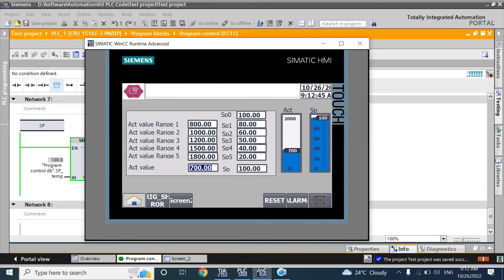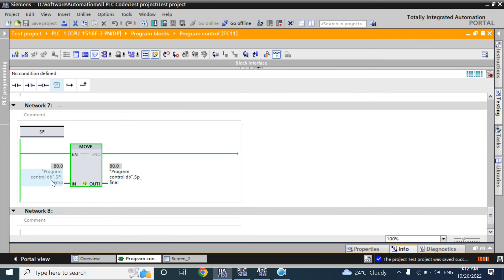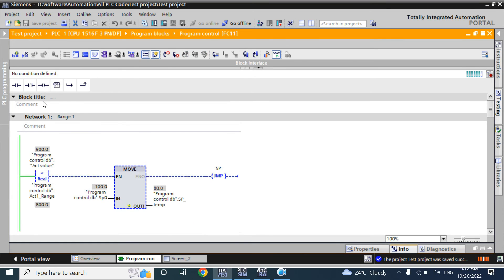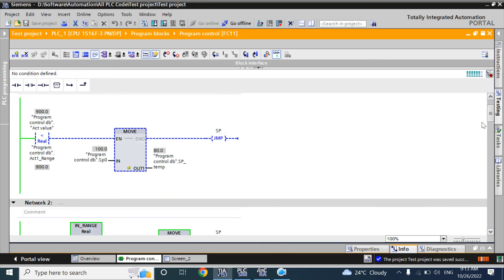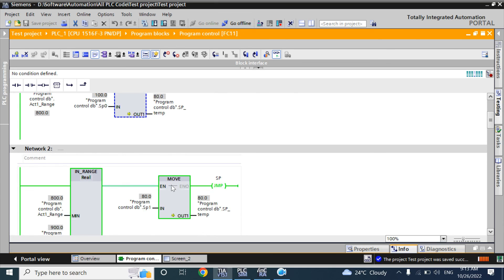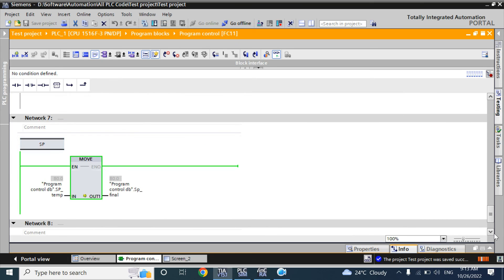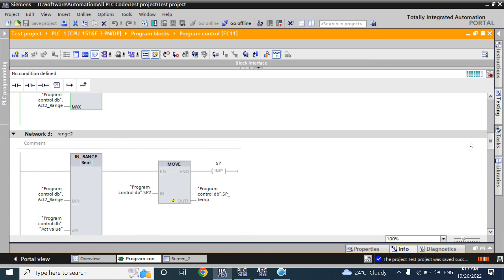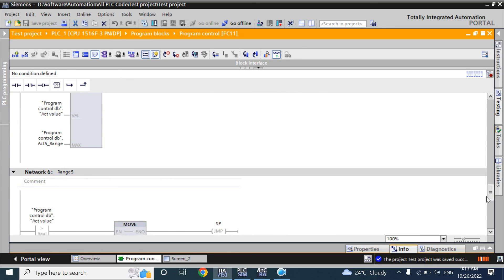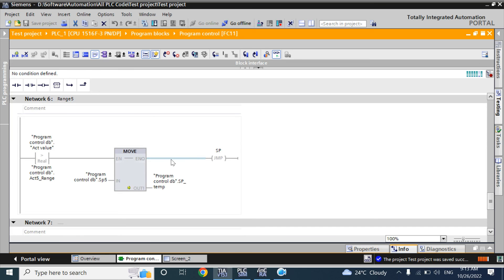Now we give the value as 900. The value is 800 here. You can see the first network is scanning — it is not true, so it will not go to jump level SP. It will scan the next network. Network 2 is now true, so it goes to jump level SP in Network 7 and passes the value 80 to setpoint final. From Network 3, networks 3 through 6 are now excluded. This way, your scan time is less by excluding those networks and your program execution is faster — that is your program control.